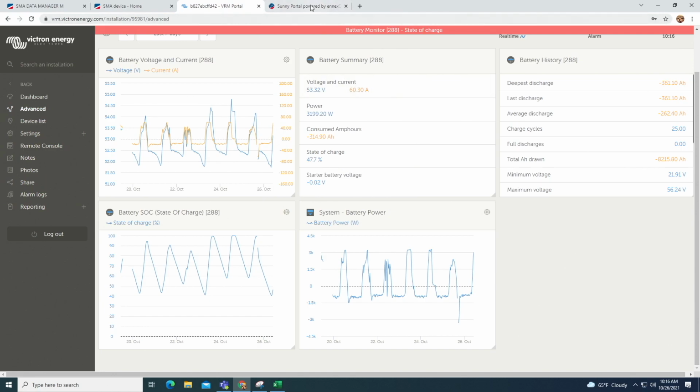I don't want to have too much charge current coming to the battery, especially when it gets full. That's where I'm concerned about this current. It's not when it's depleted, it's when it's full, and you just don't want the cells to pop over a given value, which I think is 3.65 volts for the lithium iron phosphate.